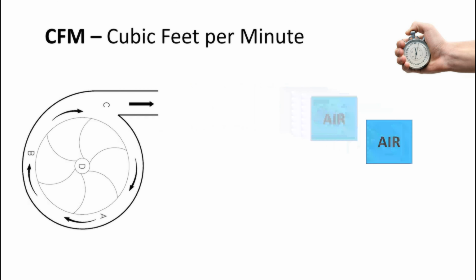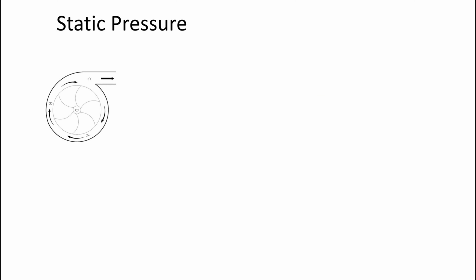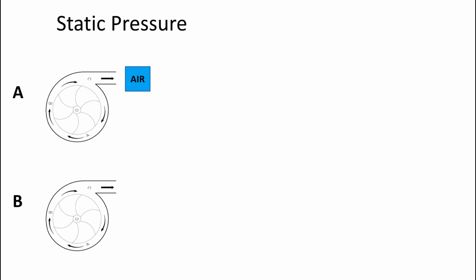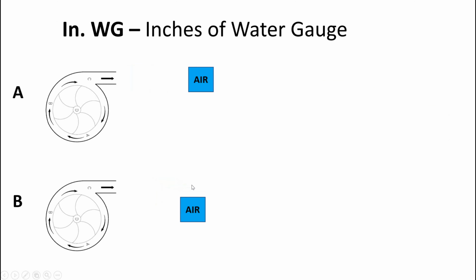Let's talk about static pressure. The static pressure is a resistance to airflow, or in other words, how well the fan can fight this resistance. Let's check an example. We have fan A and fan B. Fan A is able to push air like this, and fan B is pushing air like this. By this animation, we can see that fan A is able to push air against higher static pressure than fan B. Static pressure is measured in inches of water gauge.